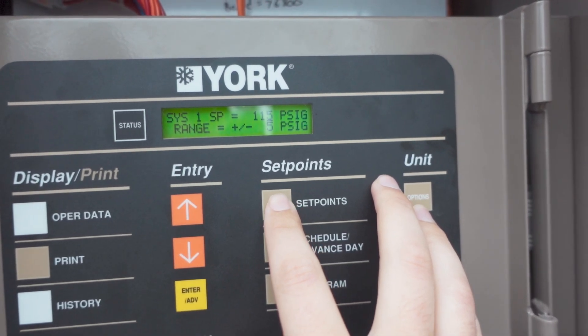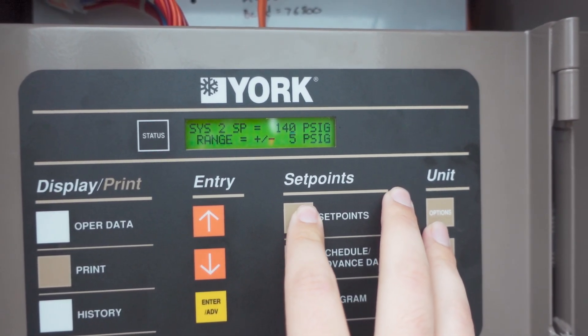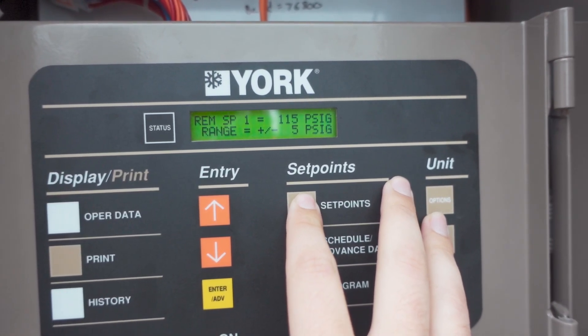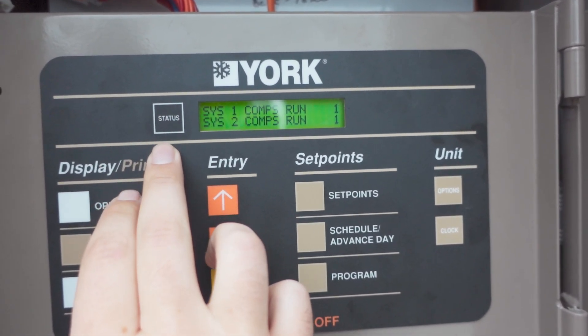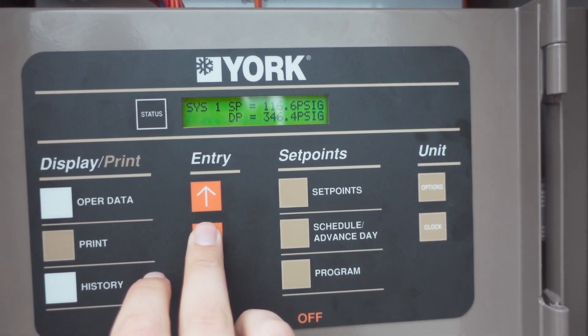One key concept: suction pressure tracks with the actual load. As load goes up, suction pressure follows when we keep compressors consistent, and inversely, as load drops, suction pressure drops with it. Keep in mind suction pressure is just another way of expressing saturation — as load goes up, saturation goes up; as load comes down, saturation follows.